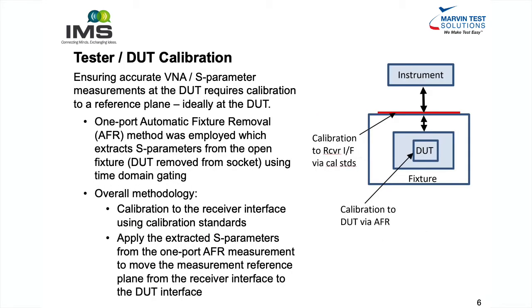Ensuring accurate S-parameter measurements requires calibration to a reference plane, ideally located at the device under test. Using time domain gating, an automated fixture removal, or AFR, method was employed to extract S-parameters from an open fixture with the DUT removed from the socket. An initial calibration to the receiver interface was performed using calibration standards. The extracted S-parameters from the AFR measurement were then applied to move the measurement reference plane from the receiver interface to the DUT interface.